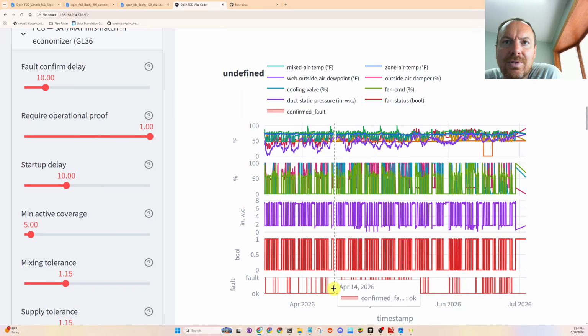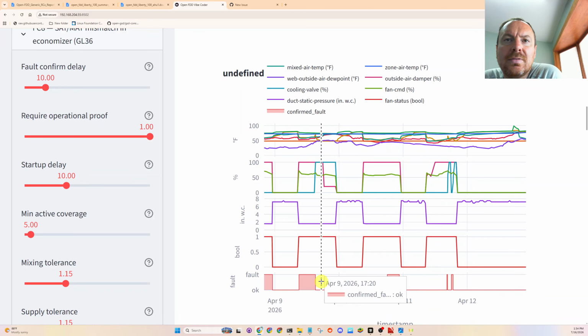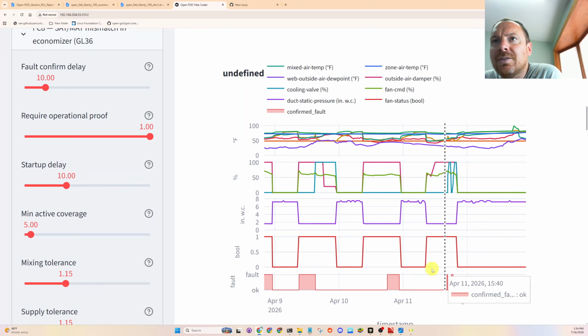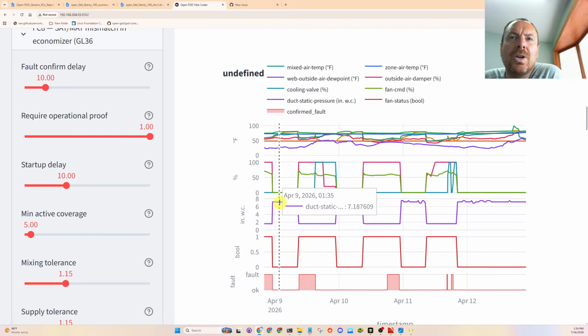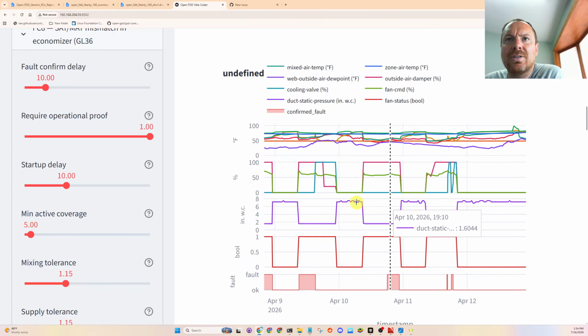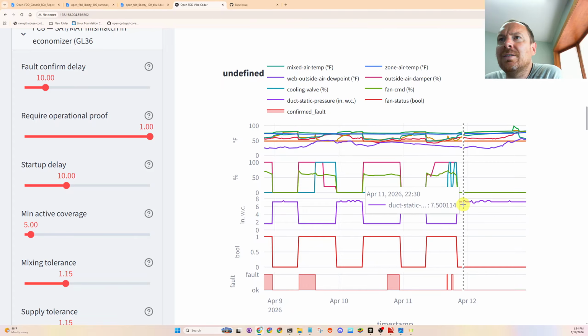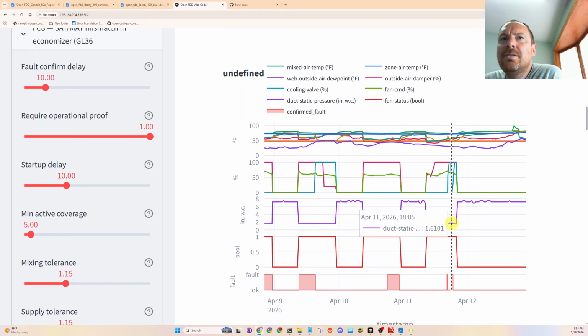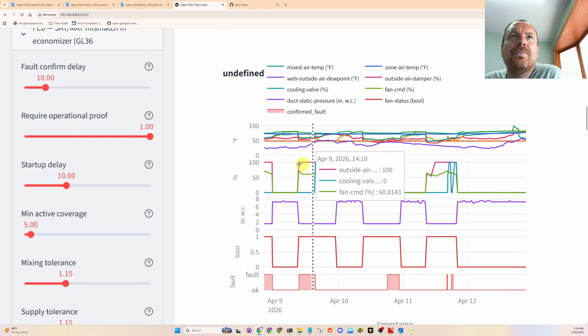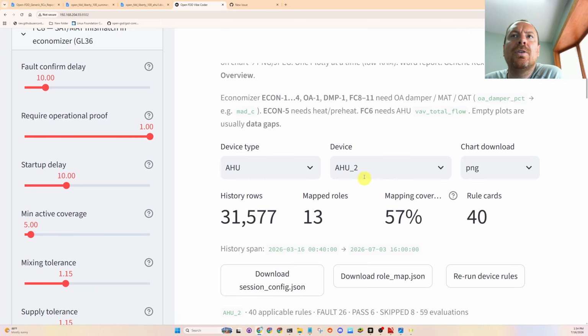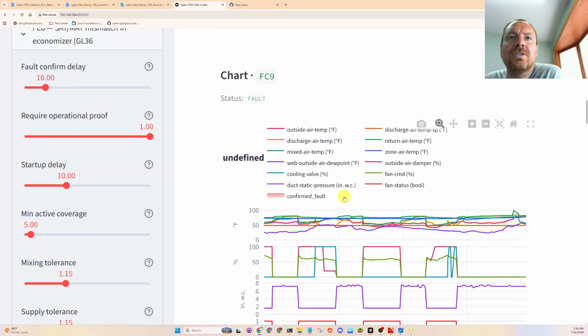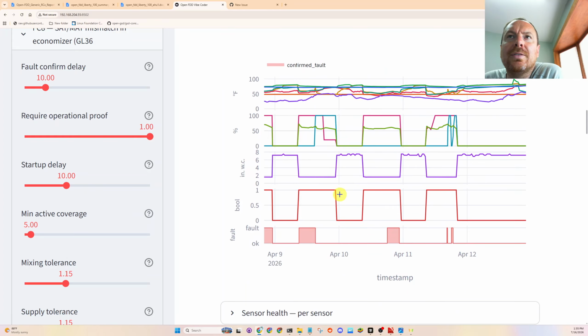So kind of early in the data when it would be nice and cool outside. Okay, so we have fan running, which is good. We're only flagging faults when the fan is running. Oh, this is air handling unit 2 with this really weird duct static pressure issue. Man, what the heck? Oh yeah, you're in unit 2. Okay, we'll have to look at this on both 1 and 2. But let's just zoom in here.